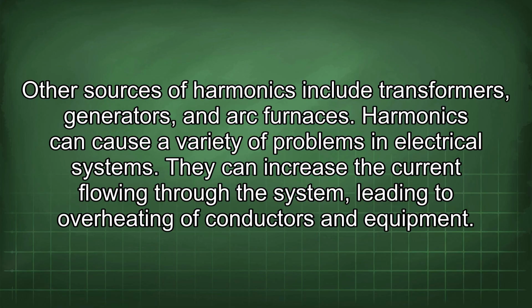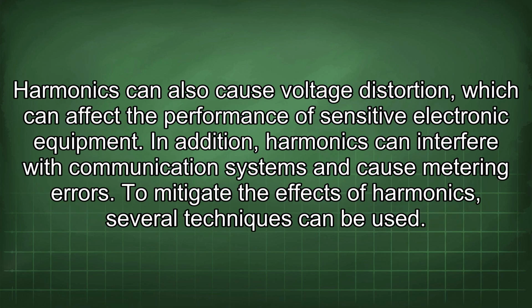Harmonics can cause a variety of problems in electrical systems. They can increase the current flowing through the system, leading to overheating of conductors and equipment. Harmonics can also cause voltage distortion, which can affect the performance of sensitive electronic equipment. In addition, harmonics can interfere with communication systems and cause metering errors.